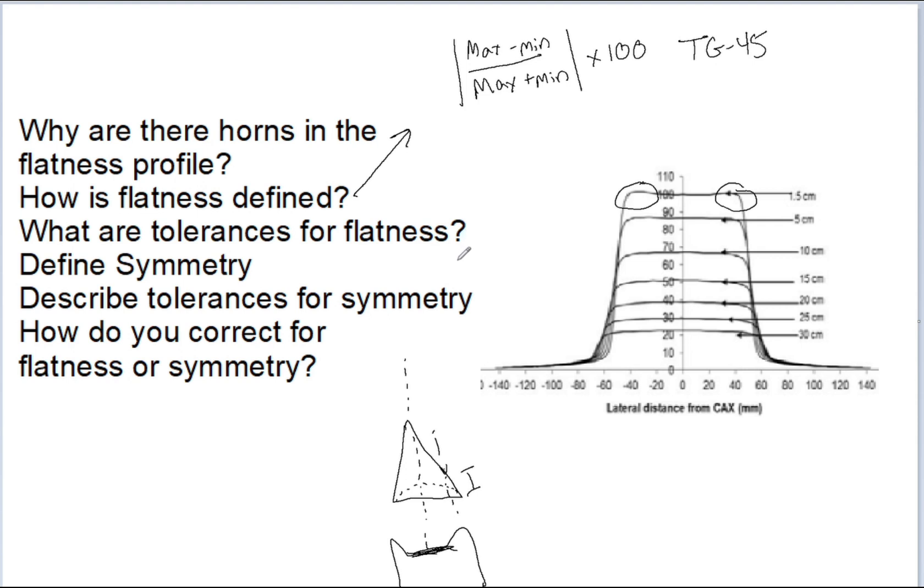Symmetry is defined as the degree of similarity between the isodose curves on one side of the central axis compared to the other side of the central axis. This is also defined over 80% field size at a depth of 10 cm. And typically, just like the flatness, this can be determined different ways.